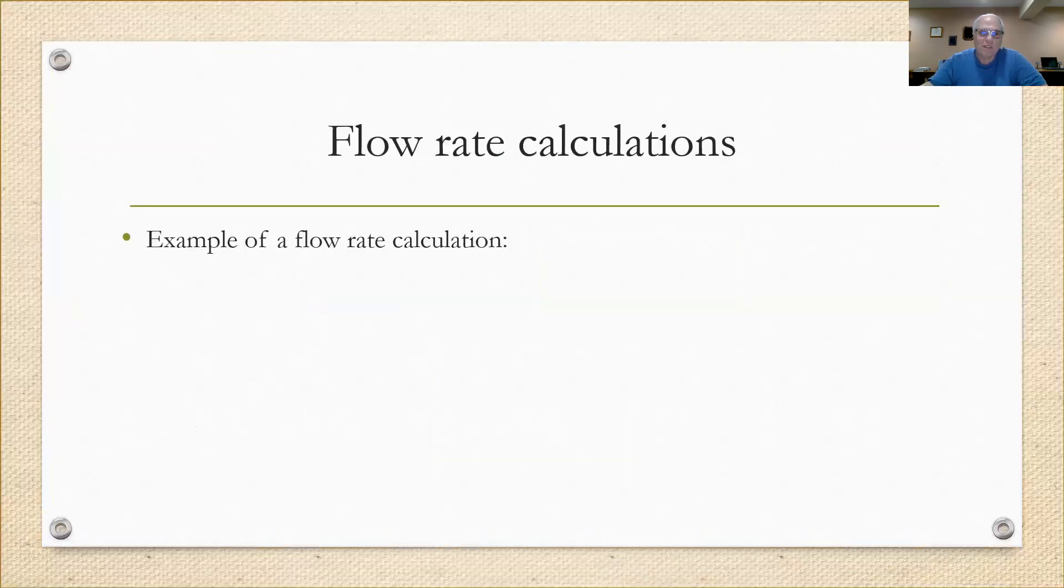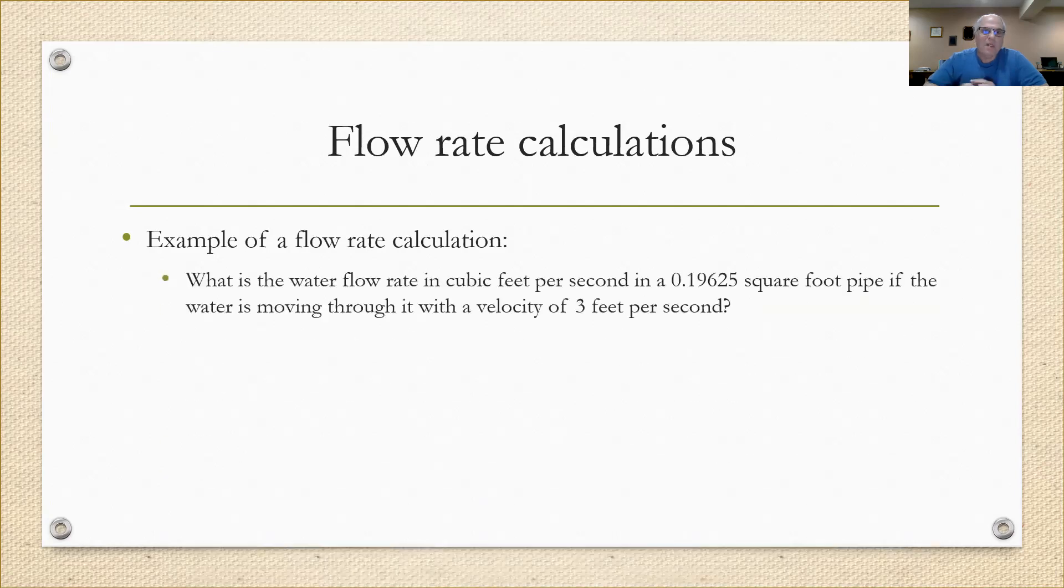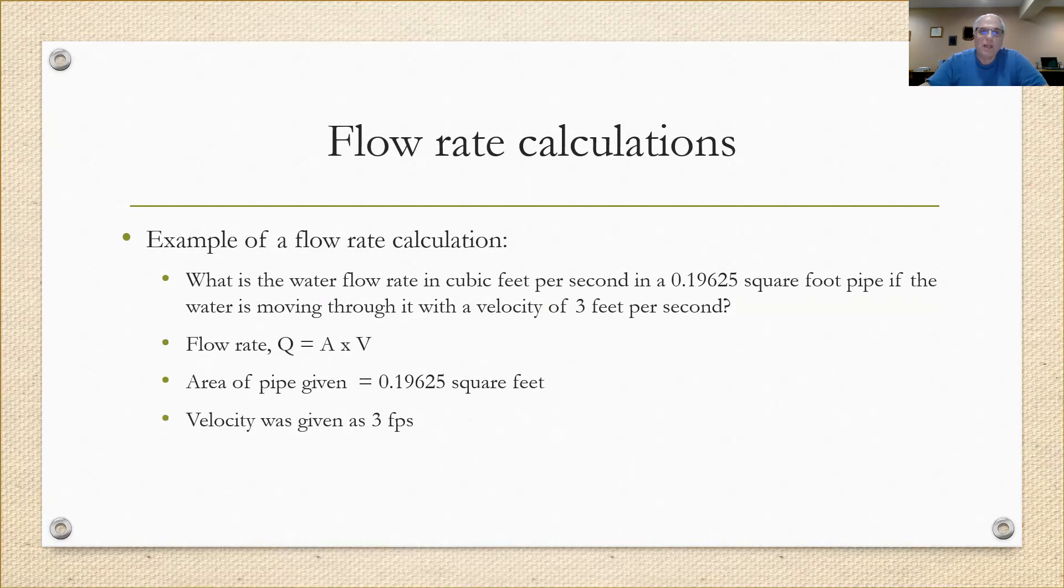Now here's an example flow rate calculation. What is the water flow rate in cubic feet per second in a pipe that has 0.19625 square feet of surface area, with water moving through that pipe at a velocity of 3 feet per second? When I set this up, I put my formula: Q equals A times V. The area of the pipe was given to me at 0.19625 square feet, velocity at 3 feet per second, so I multiply 0.19625 square feet times 3 feet per second, and I get 0.589 cubic feet per second. If I wanted to change that, I would multiply by 7.48 to get gallons per minute.